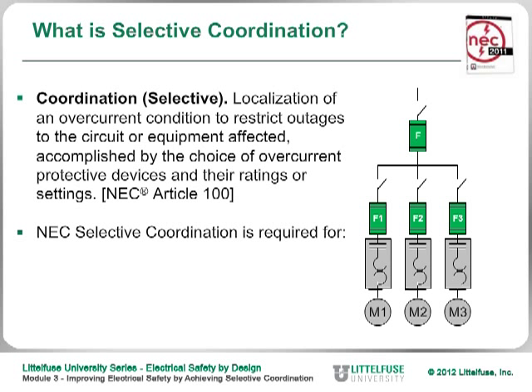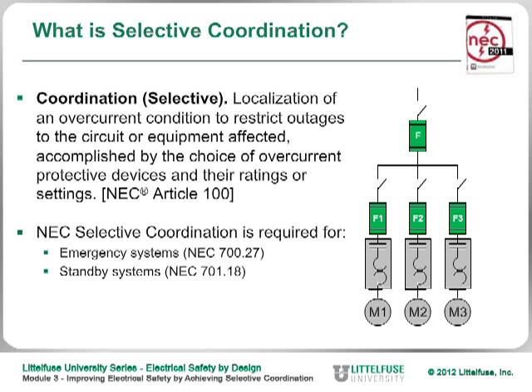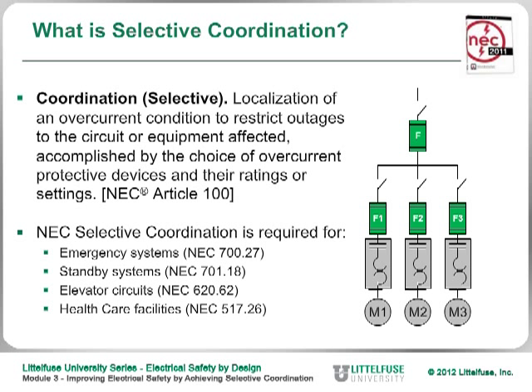In fact, selective coordination is actually mandated by the NEC for things like emergency systems, standby systems, elevator circuits, and health care facilities. In 2008, they added a new category called critical operation power systems — for buildings that must operate during national emergencies like 9/11 and so on.